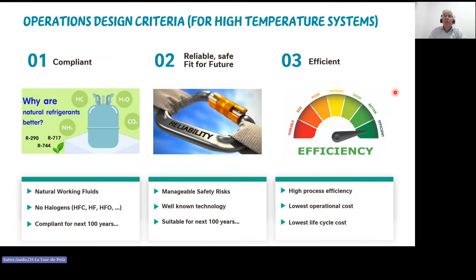Then, of course, in operation, most important: reliability, safety, and fit for the future. We have to see that the systems we are installing now are suitable again for the next 100 years. And then efficiency: we always have to aim for the highest unit operation efficiency, highest COP, lowest operational cost, lowest life cycle cost, because this will make our management support heat pumps or not. And I'm coming to the last slide, which is this one here. It's a kind of 3-stage set of recommendations. Make sure we have the right sequence in our decarbonization strategy. First, reduce. Second, rethink. And then at the last, it becomes replace.